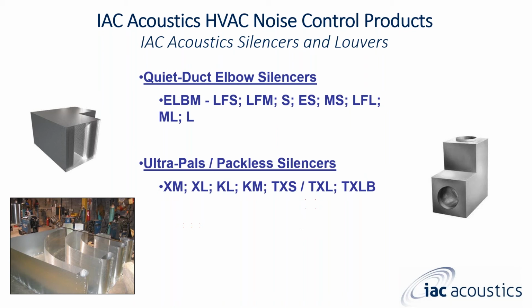We also have our Ultra Pals packless silencers, standard rectangular type, which is the XM, XL, KL, and KM. Again, there is no infill. Behind this, instead of a standard perforated material, which is 23 holes per square inch, it is now 86 holes per square inch. So again, smaller, finer holes per square inch. There is no infill material whatsoever. Packless silencers have no fiberglass, no cotton, and no mylar liner. It is the perforated material, the baffle thicknesses, and the open air passages that create the actual insertion loss.